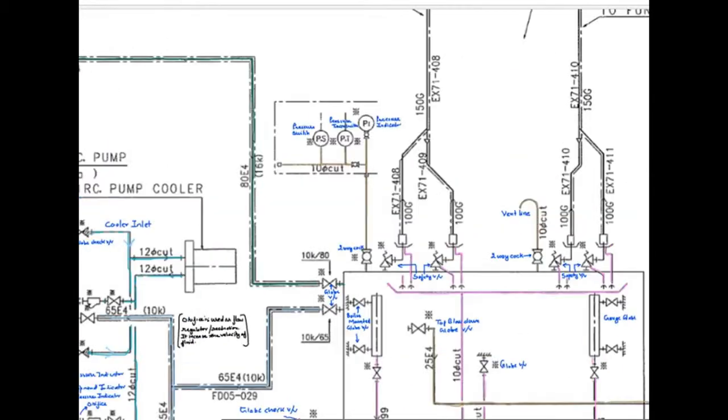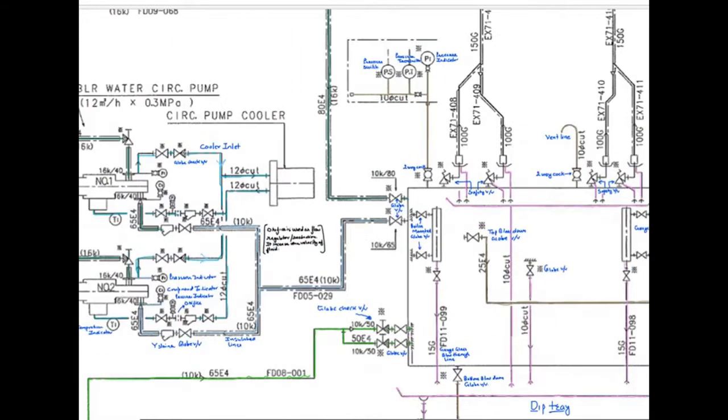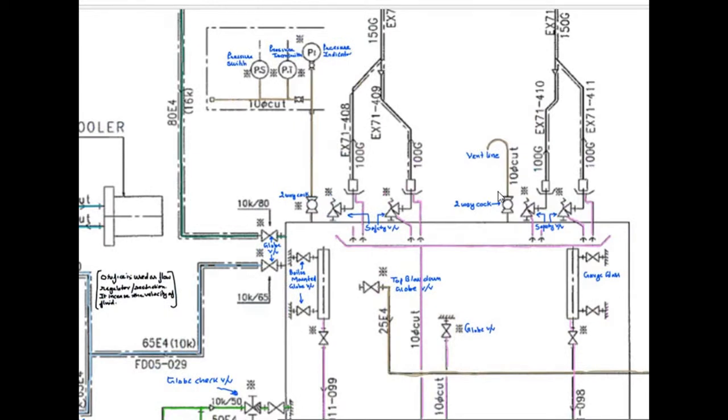On the top side, we can see the safety valves are provided 1, 2, 3 and 4. These safety valves, when lifted, they are connected to the funnel. All the exhaust steam goes to the funnel. And the condensate or the leakage if any is present, it will go to drip tray and goes back to engine bilges.